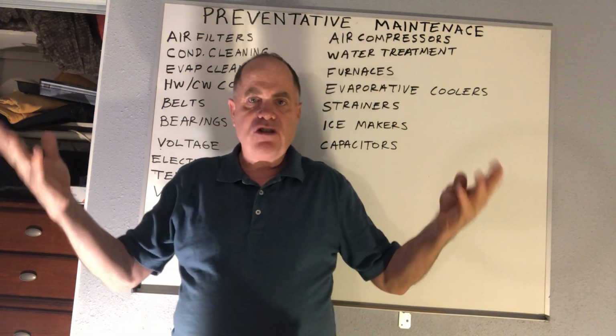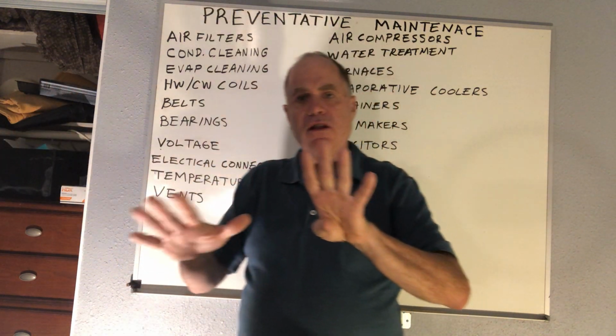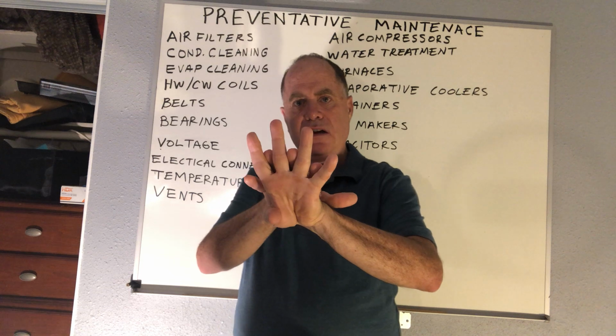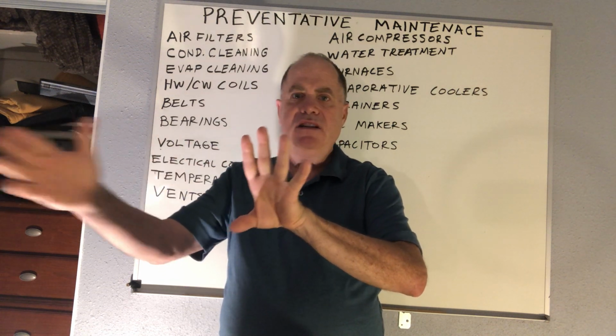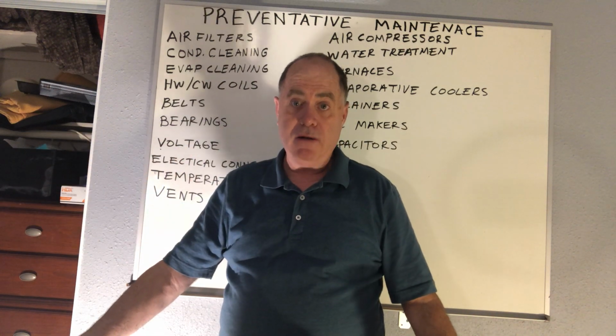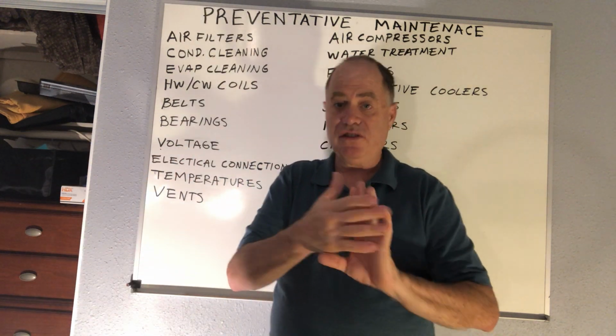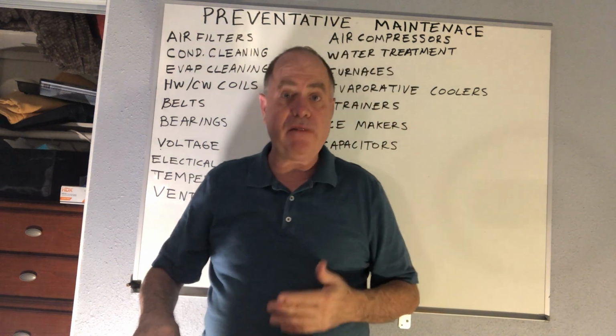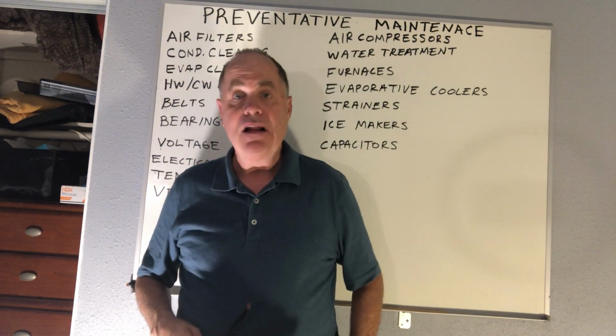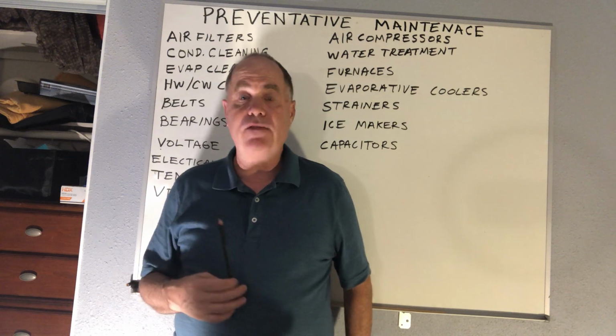and burners and stoves and all of this. And those kitchens have grease vapor, and the grease vapor tends to stick to coat the condenser fins, and then any dust that comes, and these are near the floor, and then any dust will just stick to that. So sometimes those would have to absolutely be cleaned like every 60 days or something like that. Otherwise, it's going to have a breakdown.